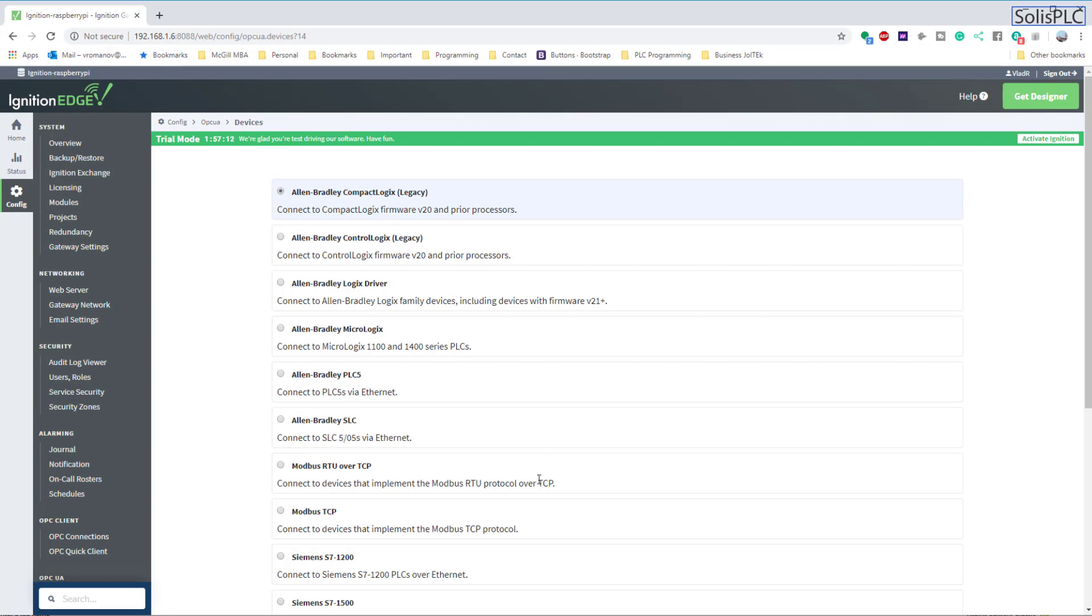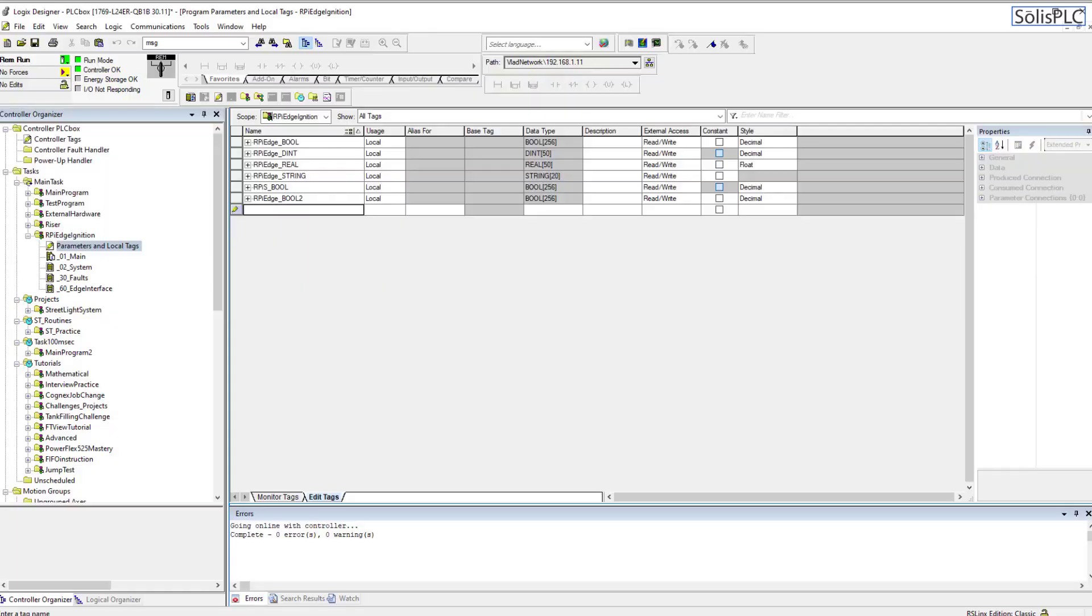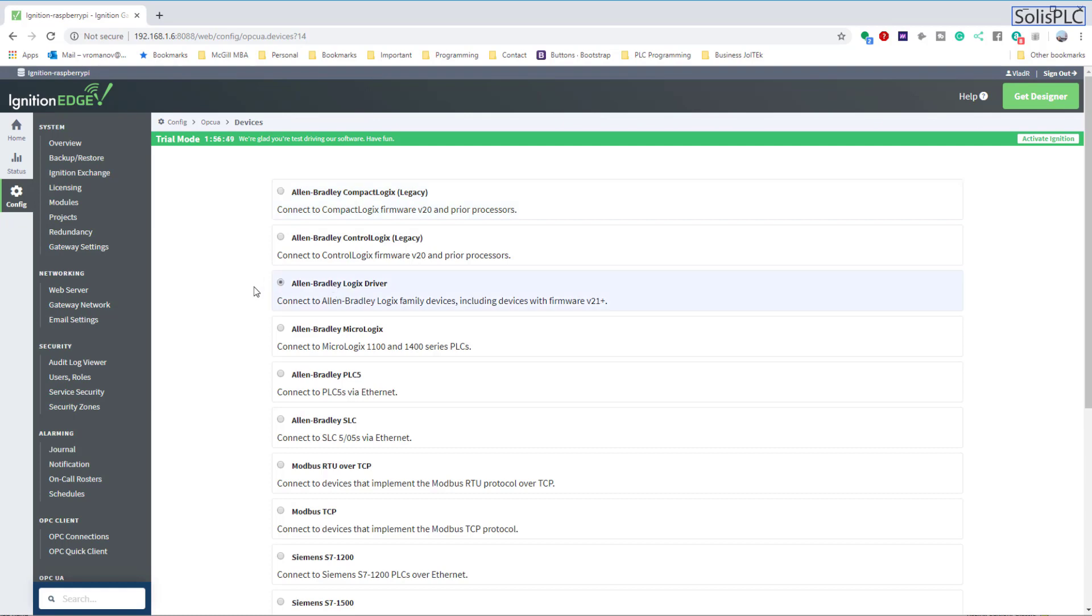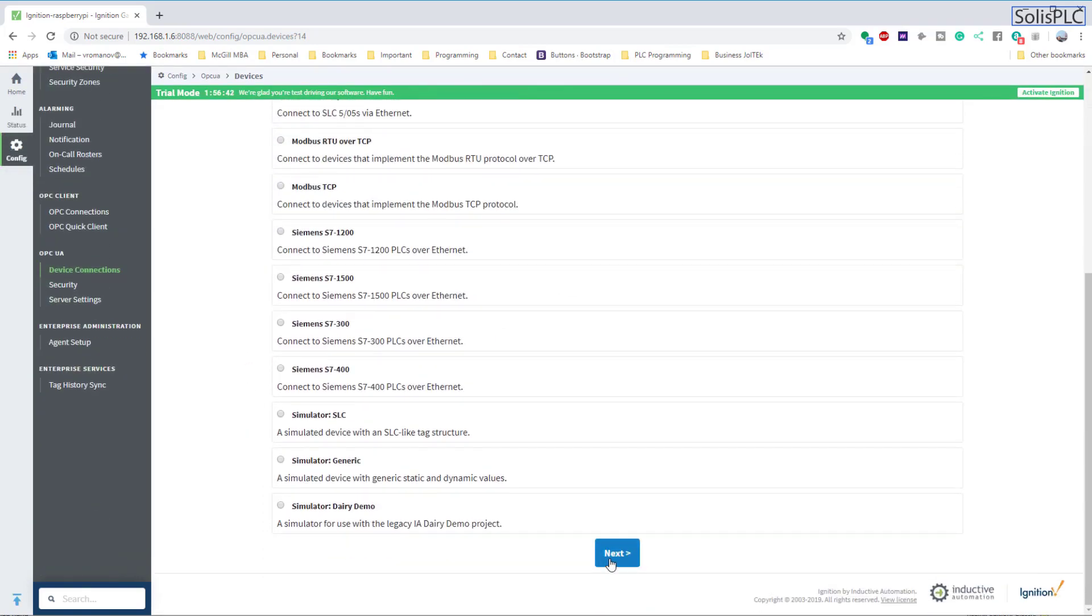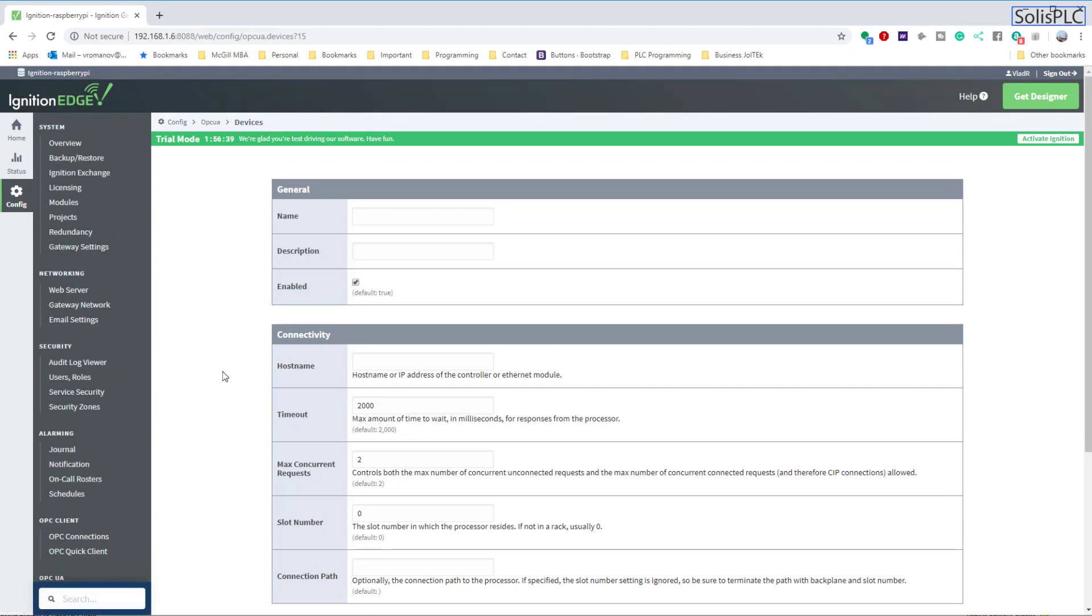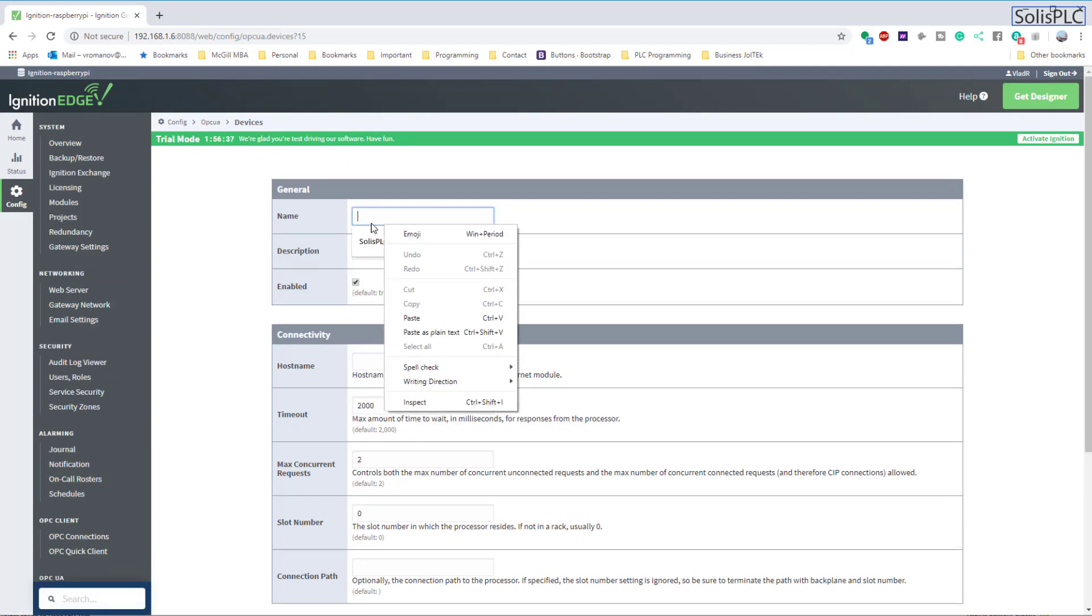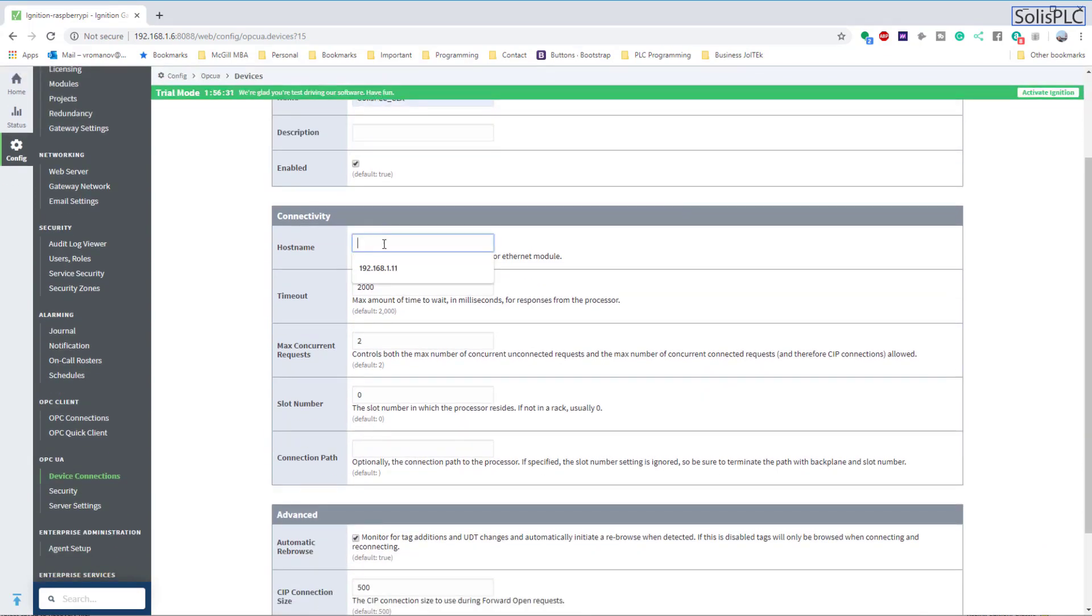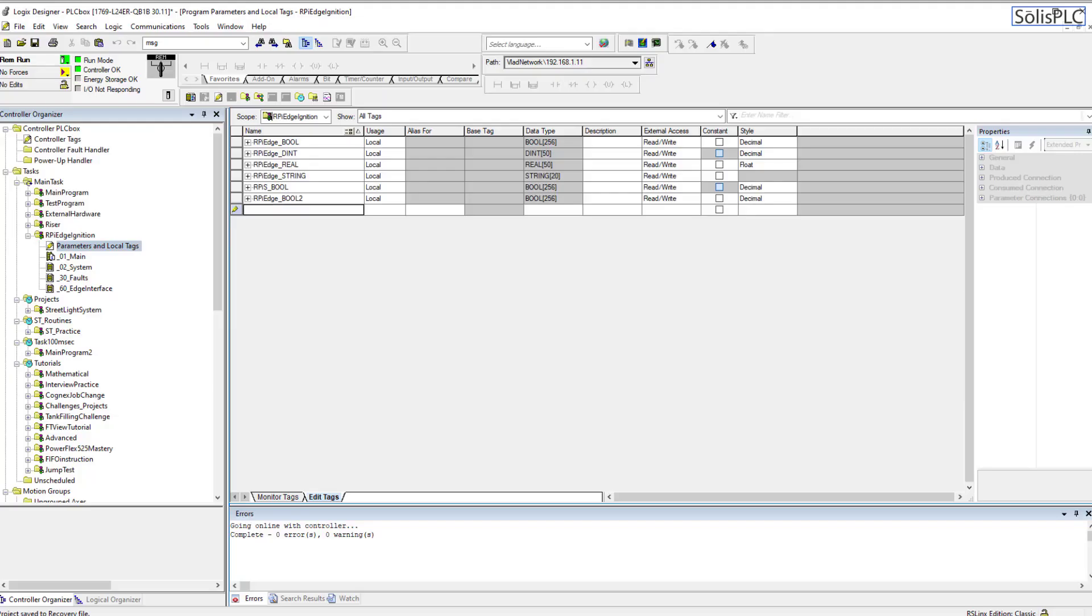The driver that we're looking for - and you do need to pay attention to the firmware revision - so here it says the default one is 'Connect to a CompactLogix firmware 20 and prior'. Now remember that if we switch back to our CompactLogix, the version is going to be listed all the way at the top here, which is 30.11. So it's definitely not prior to version 20, it's definitely not a ControlLogix with V20 and prior. Next we have 'Connect to Allen Bradley Logix family devices including devices with firmware 21 plus', which is exactly what we're looking for. So we're going to select this driver. Like I said, pay close attention to the type of PLC you're using. I'm going to scroll down and press Next. At this point I'm going to give the PLC a name - it's already in there. The description is optional. Enabled - that's what we need.